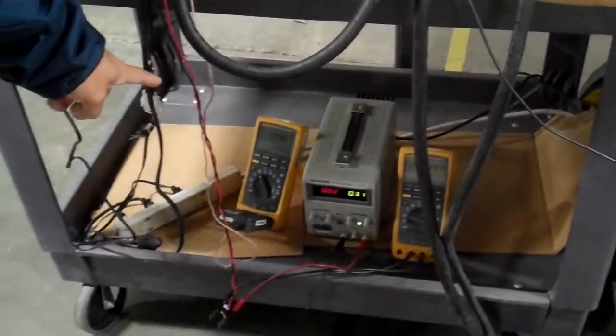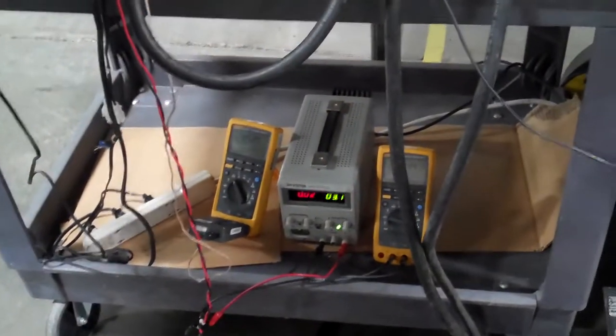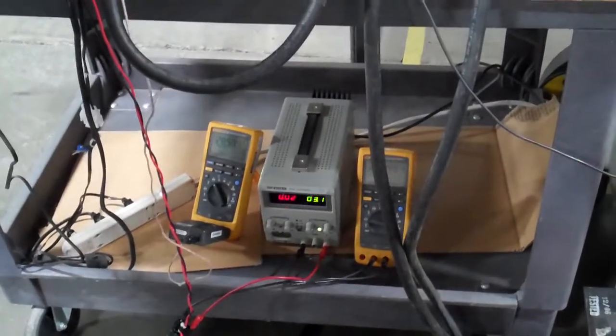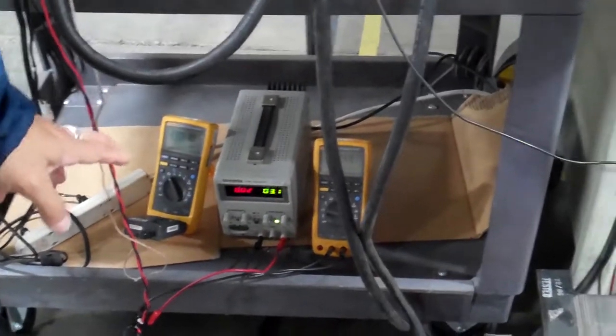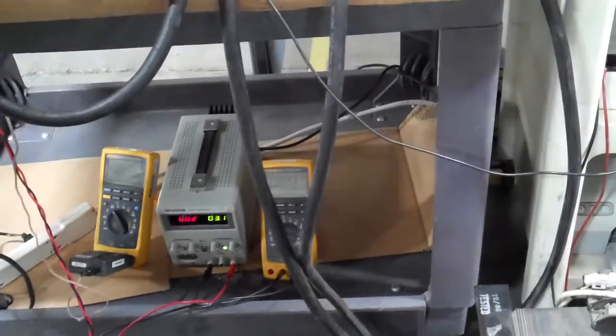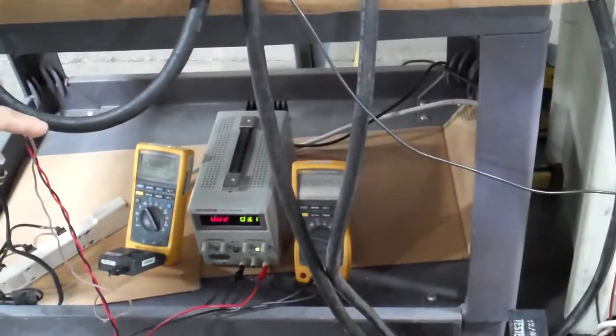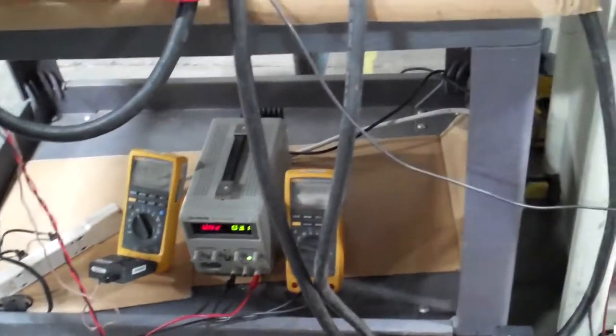Right now we have 28.5 degrees heat, and it is increasing. We also have 20 milliamps, so we are firing our board at minimum delay angle, although we wouldn't see any output because the output is shorted.